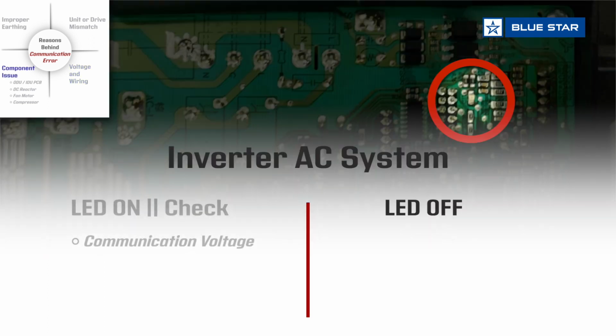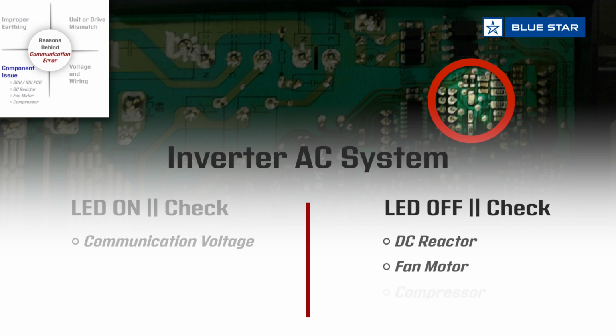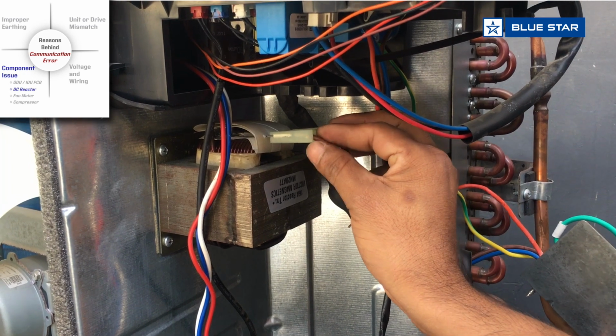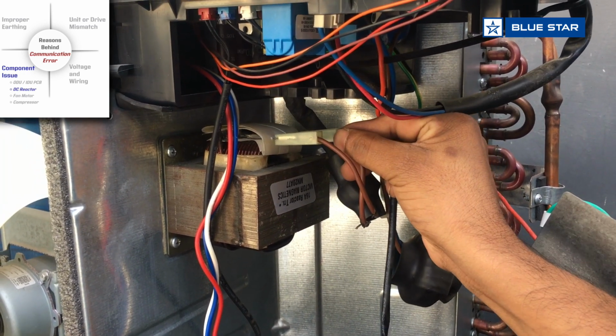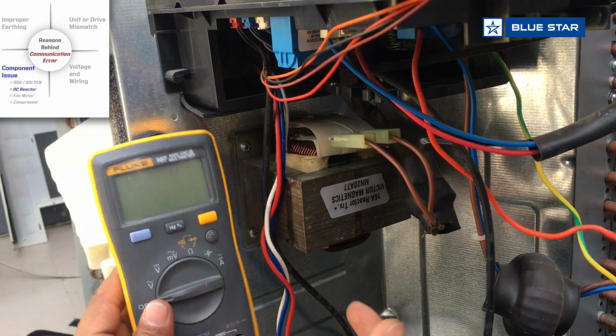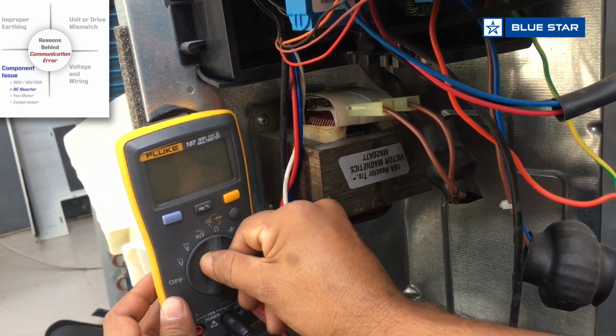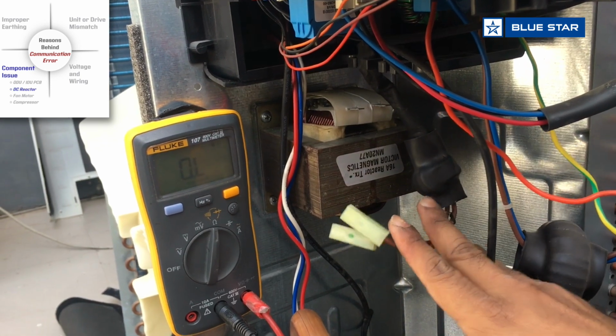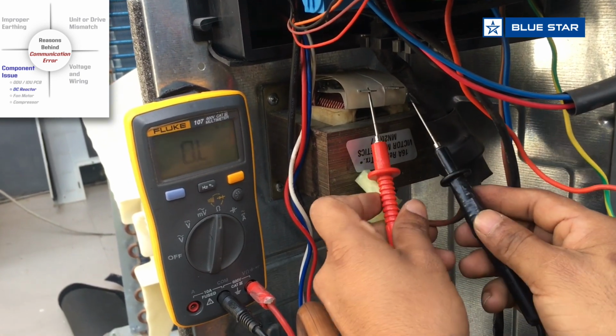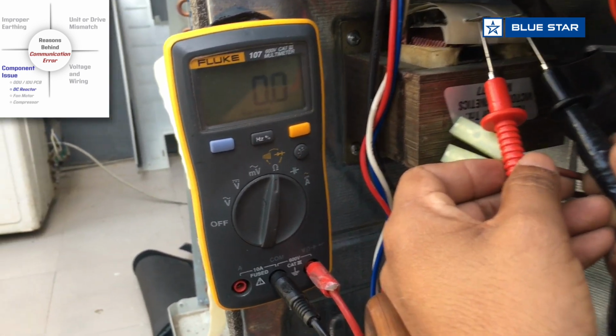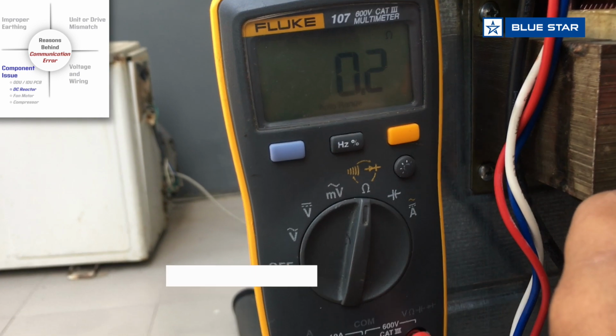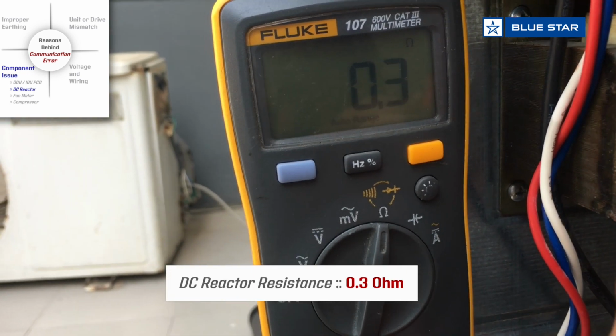Now let's look at the other possibilities. If the ODU drive LED is off, check the DC reactor, fan motor and compressor. DC reactor. First check for loose connection. Then check the resistance of the DC reactor. It should be between 0.1 to 5 ohms. If it is not within the range, replace it and check if the unit still shows communication error.